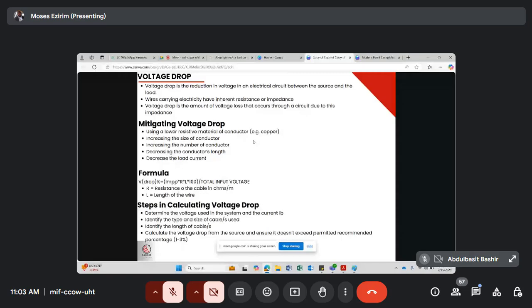When you increase it, obviously, for example now the length where you pull 100 meters, if you realize that the voltage drop is not within the limit, see how you can reduce the length. Once you do that, calculate the voltage drop again and it will be within the limit. You can also mitigate voltage drop by decreasing the load current.